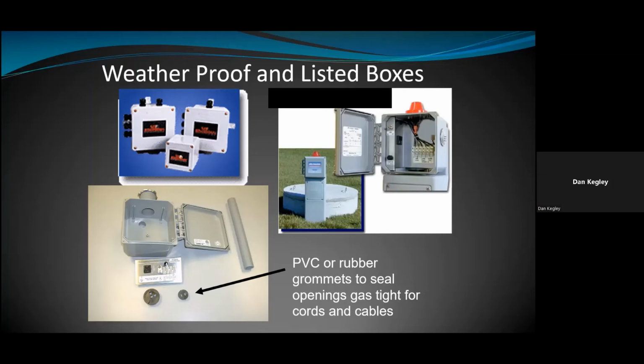If you had a large enough junction box, you could put a little metal handy box, about 2 inches by 3 inches, have your UF wire going into the handy box, and then have a single receptacle inside that little handy box. You could create your own receptacle inside that box for that cord connector to plug into, and that would be perfectly acceptable. Gotcha. So a little handy box with the receptacle on the end, versus a cord connector used on a UF wire, which is not a listed product for that purpose. Right. Let's see what else.